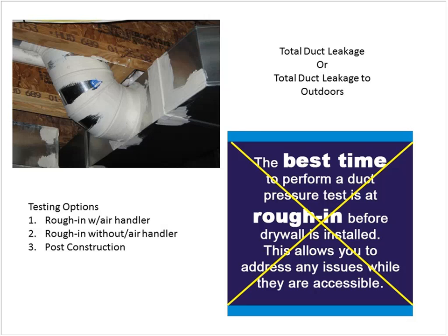On February 8th of this year, when the new code went into effect, we outlined the testing options that are in the code for ducts. As I had mentioned before, the testing options are rough-in with the air handler, rough-in without the air handler, and post-construction. The common thought at that time was that the best time to perform duct leakage pressure testing was at rough-in, before the drywall was up, so that you can address those types of leaks before you cover them with drywall, so the problems are taken care of before they get covered up.